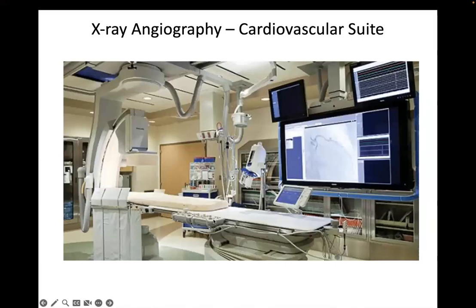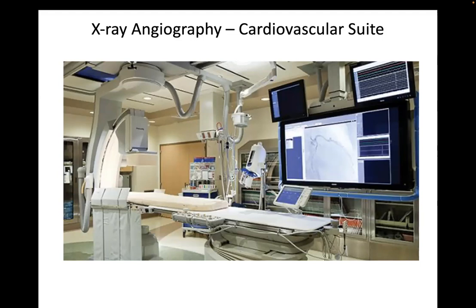This is a fluoroscopy lab. The patient table here — you can control height and position a bit — but most position control is from this large device called a C-arm, because there's a C-shape with a detector and an X-ray source. You can rotate it with multiple degrees of freedom, pan back and forth, pan up and down the table, and rotate the angle of view through the patient. This is the primary imaging modality for cardiac interventions, especially in coronaries and putting in devices like aortic valves, mitral valves, or a device to close off the left atrial appendage.